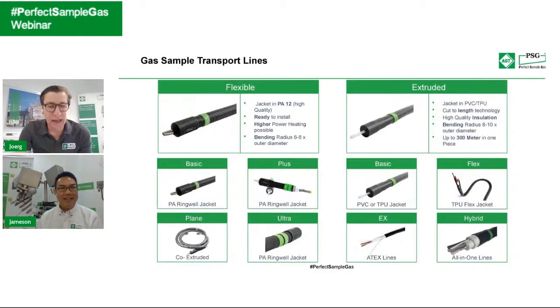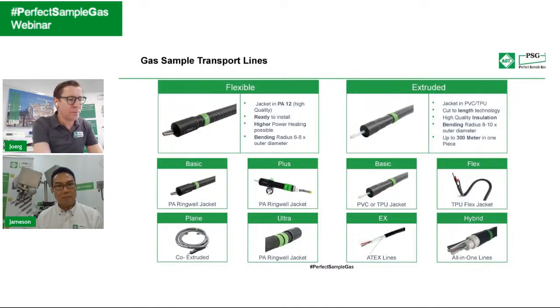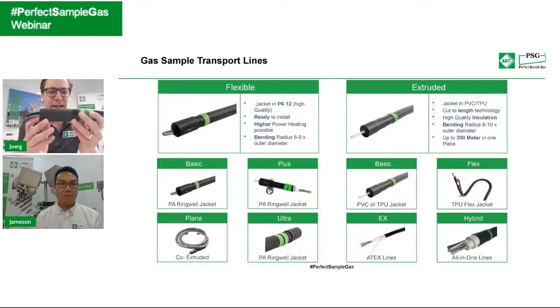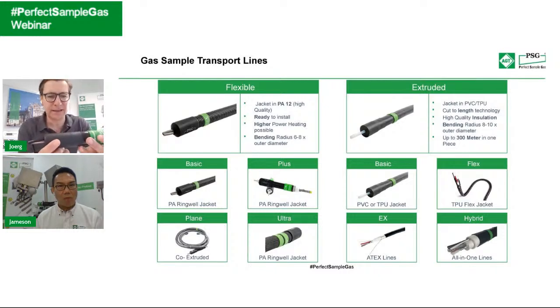You're right. Yeah, go. Then really, as we spent quite some time on the gas sampling probes, now the heated sample lines, where we gave this overview here, our main topic, sometimes underestimated. I think that's what we said so many times in this webinar. But really, the heated sample lines, and this is what we can give you as a quick fix advice: it's very often the interfaces between the different components with the heated sample line which can cause problems, especially in the field of condensation. And therefore, it's very important, if you look at the heated sample line manufactured by us, and this is just an example, even if you buy this from other suppliers, please make sure that the heating goes very much up to the end of the heated sample line.